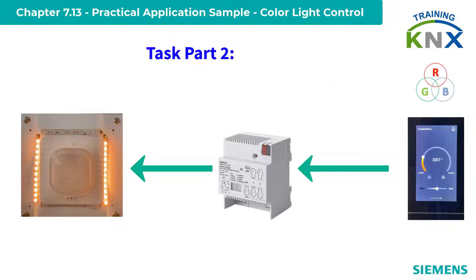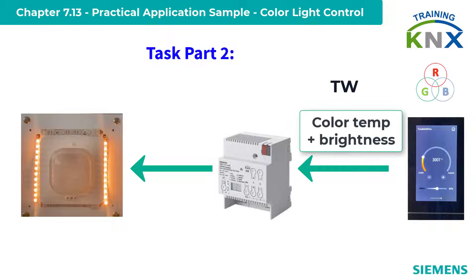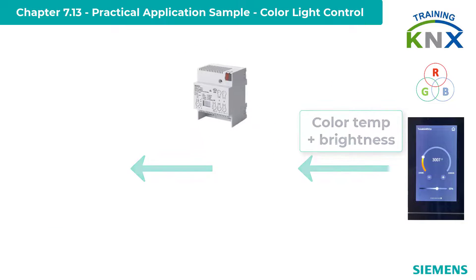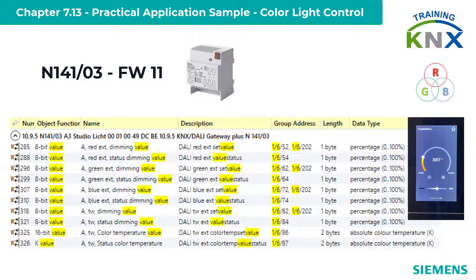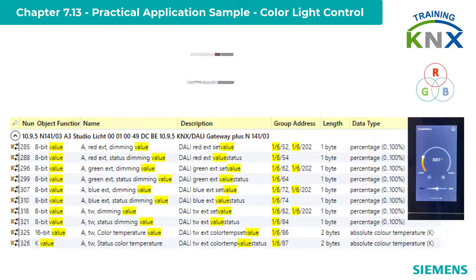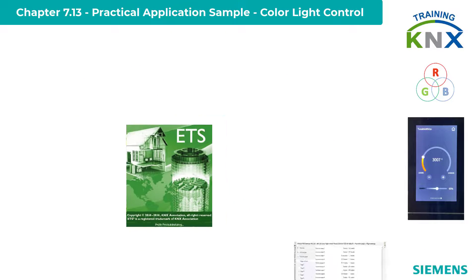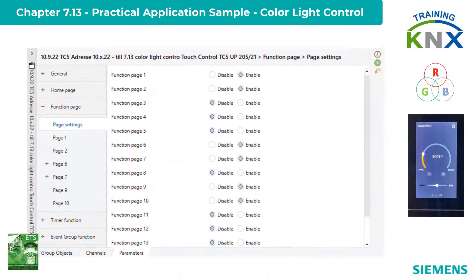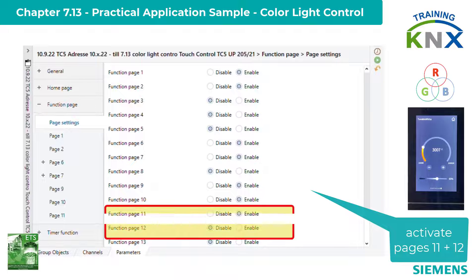As a second step, I will then put a tunable white luminaire into operation via the color temperature. The DALI gateway for this, a Siemens N141/03 with firmware 11, I have already prepared. In the ETS, I go to the page settings and release pages 11 and 12.